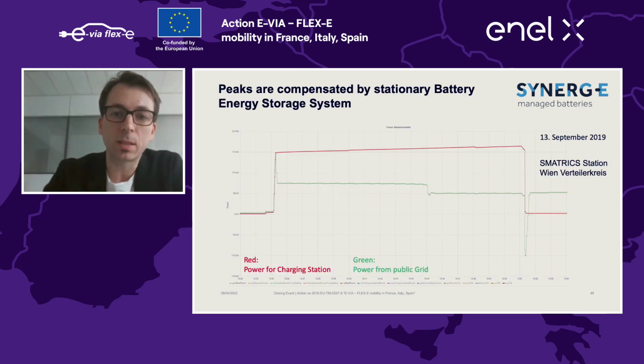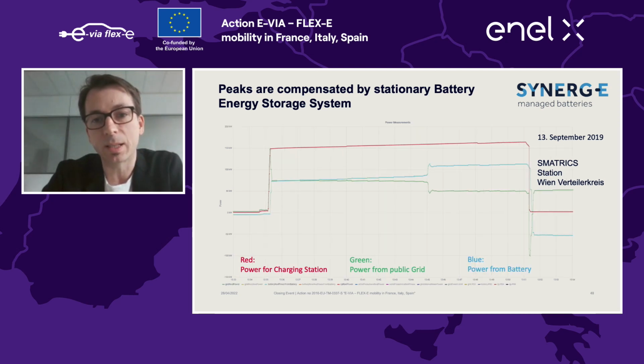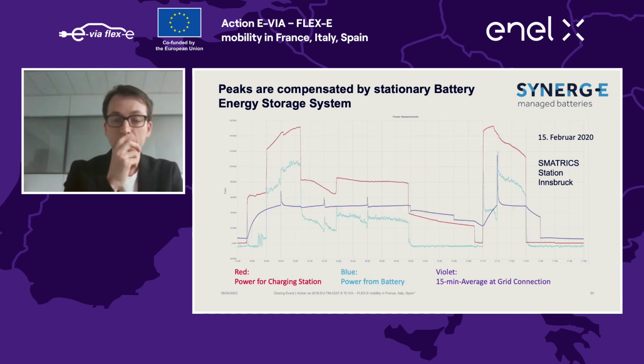Here you see this charging event from the beginning again, but this time in green you also see the power from the public grid, from the grid connection point. The difference between these two lines is the energy and power coming from the battery. On the next slide you see the blue line, which is the power from the battery. In this event, we successfully shaved the power needed from the grid to a lower level.